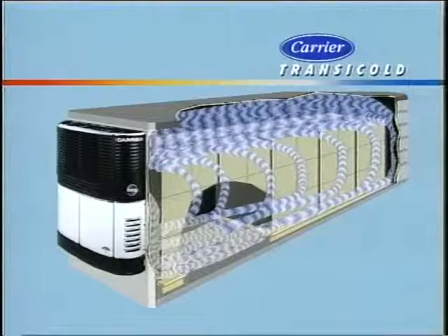To change the set point, simply press and hold either the up or down arrow key. You will notice that when the set point is above 0 degrees, there will be a plus sign in front of it. If the set point goes below 0 degrees, a minus sign will appear. The message center will show directions: up, down to scroll, then equal to save. Continue to hold the arrow key until the temperature you want is shown in the display.